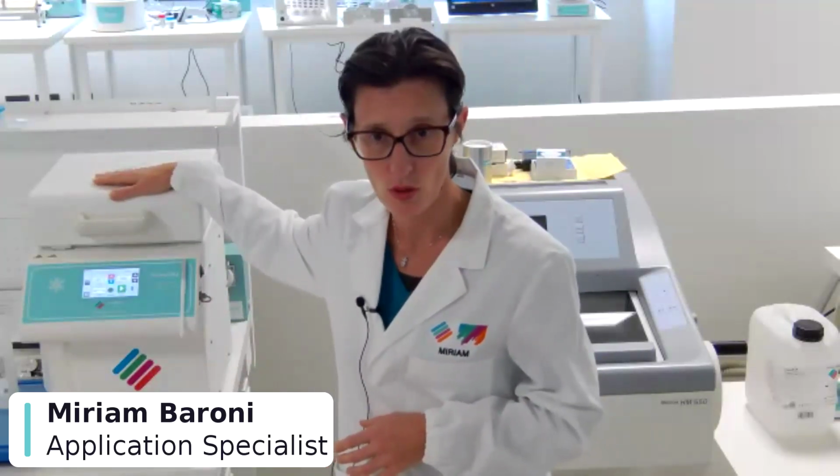In case of breast, instead, is the opposite. We need to prolong the freezing time, and we suggest to freeze for 4 minutes because the breast is an insulation tissue in the body and requires a lot of time to get cold and become hard enough to be cut in the cryostat. So for breast, we have a specific protocol in which we freeze the sample for 4 minutes in the Presto Chill.